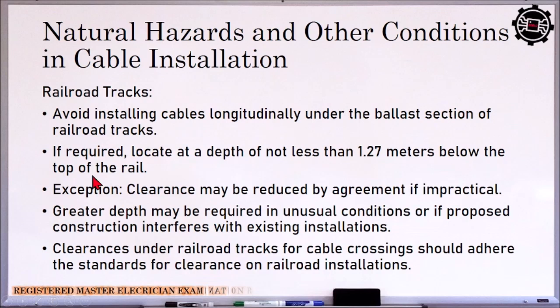No, katulad pa ito nang di-discuss natin last week. So greater depth may be required in unusual conditions or if proposed construction interferes with existing installations. Tapos yung clearance under railroad tracks for cable crossing should adhere to the standards for clearance on railroad installation. So that will be not less than 1.27 meters if magko-cross siya sa railroad. No?